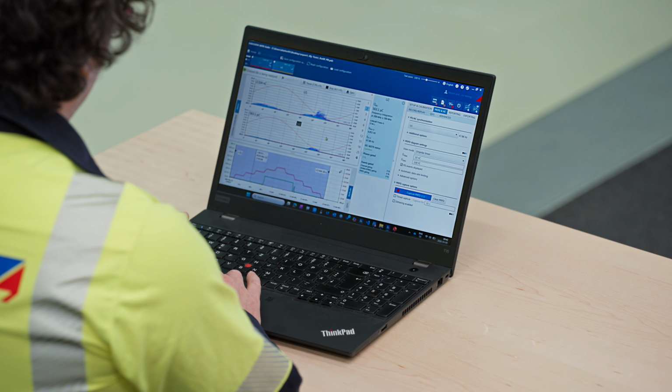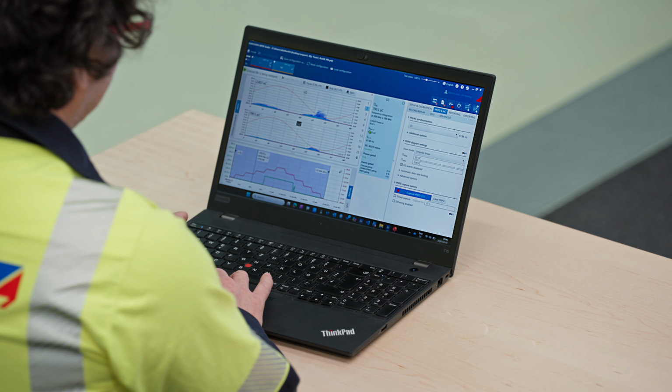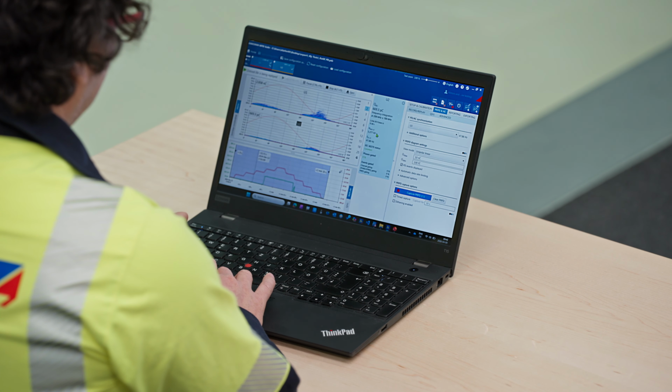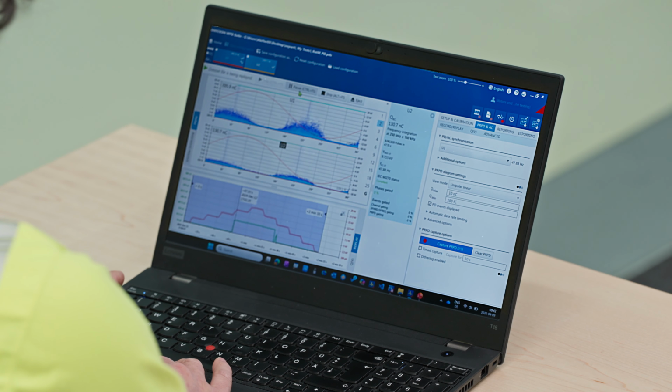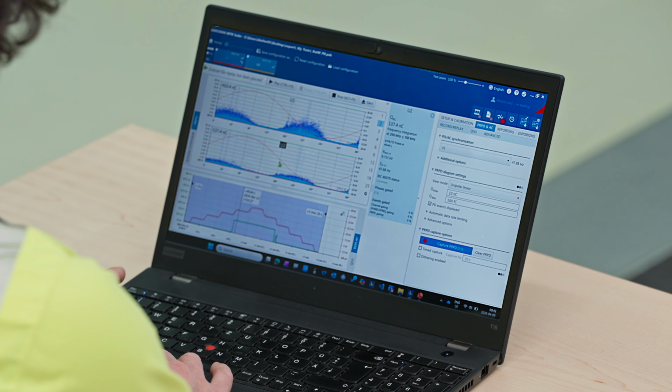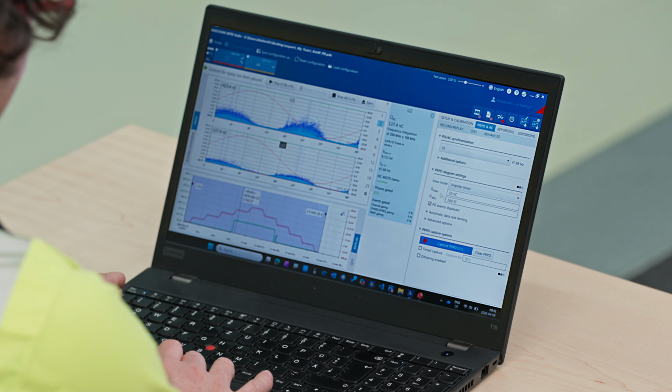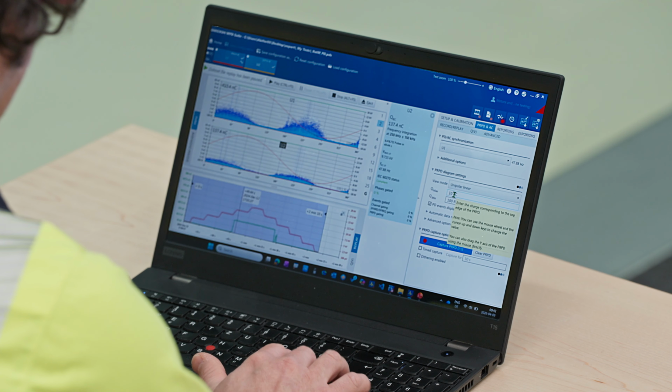and the test voltage is also visible here. It is possible to compare the measurements with previous measurements. In this case, we see that the magnitude of the PD activity is increasing dramatically, so we can make a change of the scaling here.